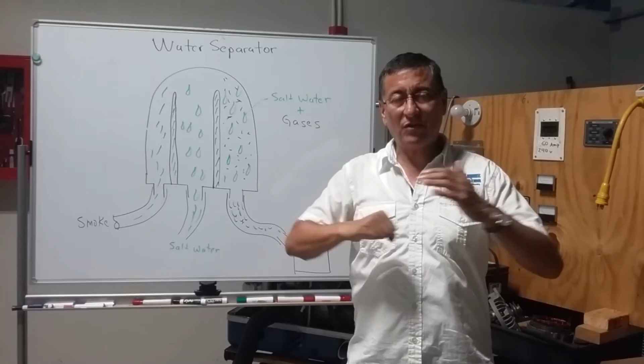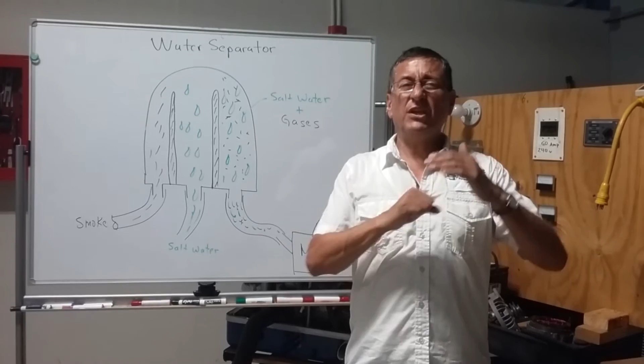Remember, you need to pass 2 lines. One for suction and the other one for return. The return line should be bigger than the supply. Why? Because the return normally returns with high temperature. Of 100% of the fuel entering the engine, 20% is used for the combustion, and the rest, after the compression in the fuel injection pump, 80% returns into the tank. What happens when the fuel is compressed in the fuel injection pump? The temperature goes up. The return fuel is returning with high temperature. What happens with the temperature of the fuel in the fuel tank after 2 hours of operation of engines and generators together? That fuel is too hot.